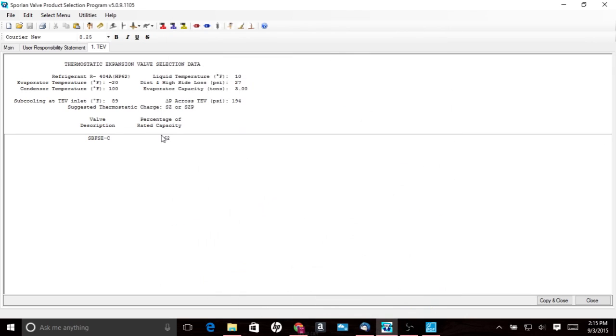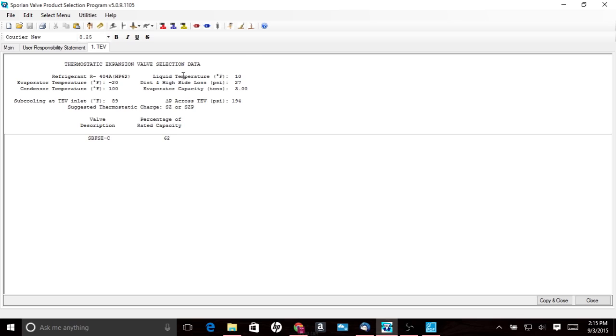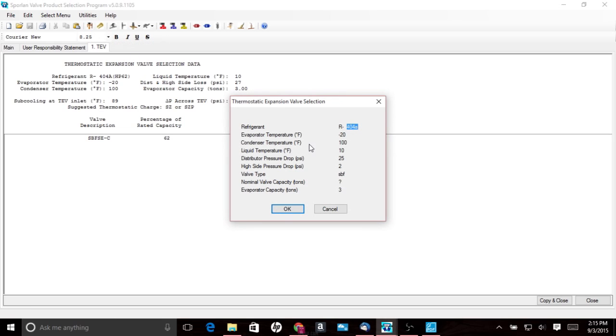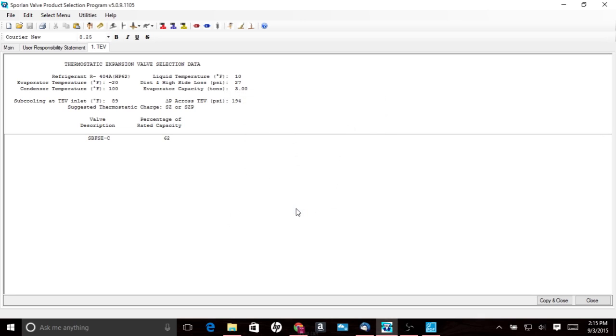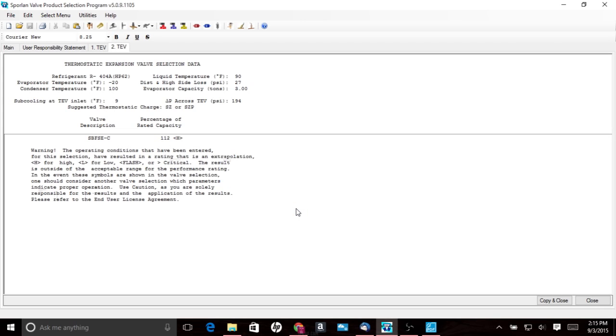Well I paused right there because I didn't get quite the reading I was looking for saying the percentage of rated capacity is 62% of the valve, and I know that's not the case. And looking up here, I see that instead of putting in 10 degrees of subcooling, I put in 10 degrees as our liquid temp, which would be 90 degrees of subcooling, be a heck of a subcooler on this system. So we're going to go back, it's really easy to do. We go back to the expansion valve selection tool. We're just going to correct our mistake here, 90 degrees liquid, 10 degrees of subcooling. And that brings up the rating at those conditions, which now puts us, as you can see here, percentage of rated capacity, 112.